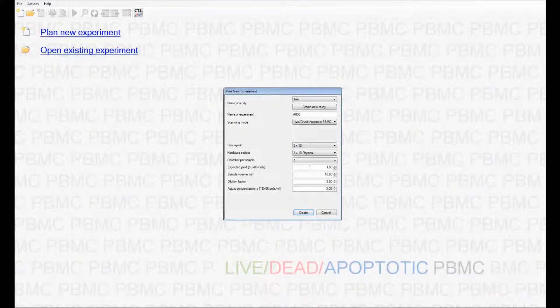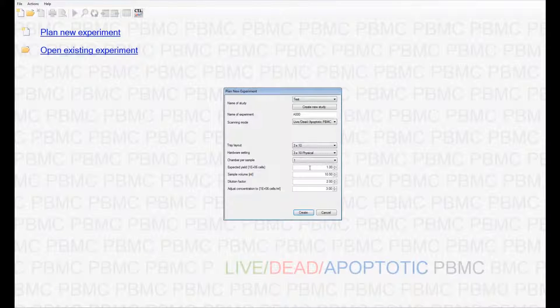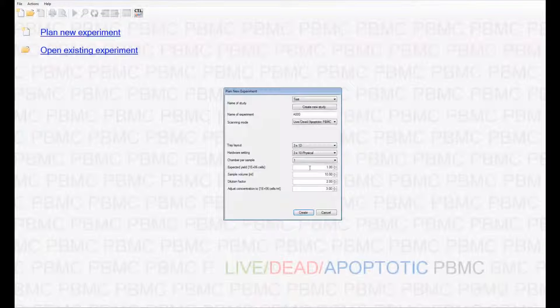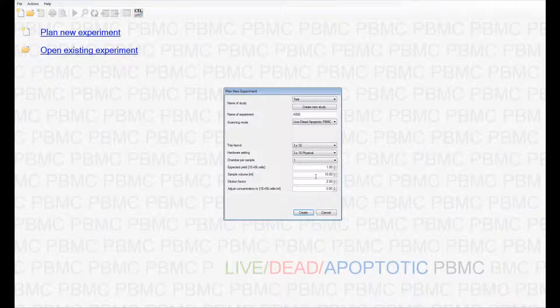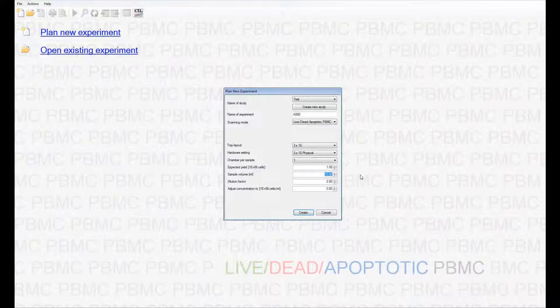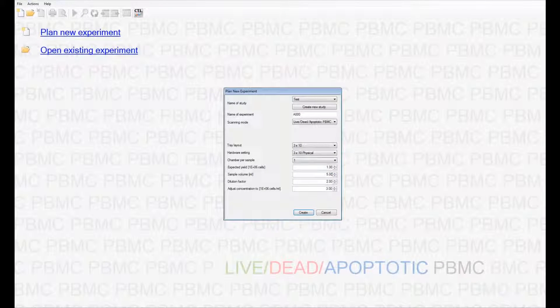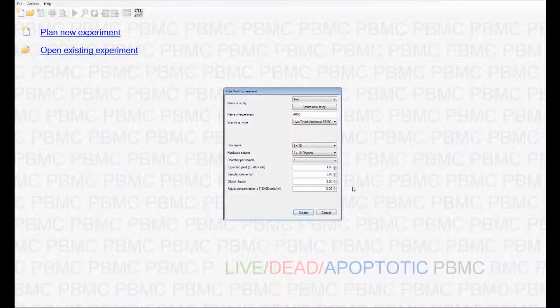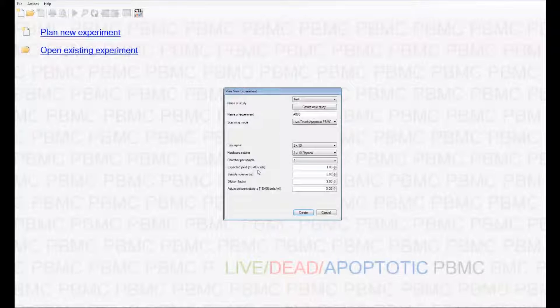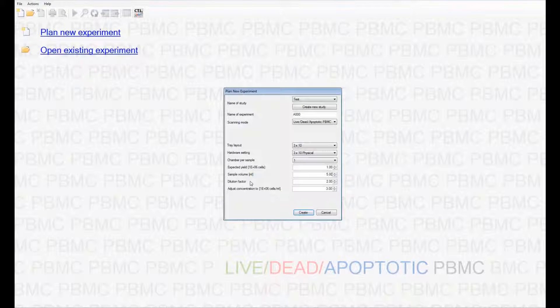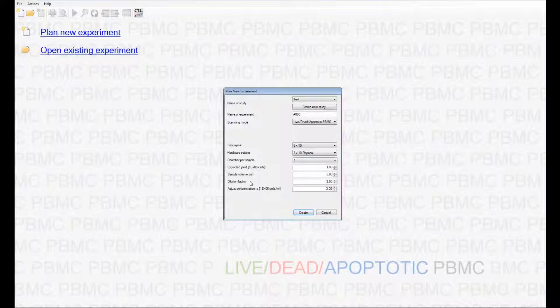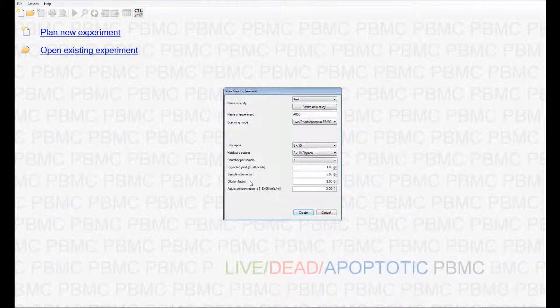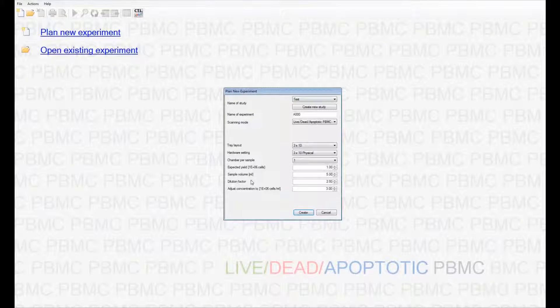A few other parameters that we should specify here are dependent on the particular cell sample that you want to count. For instance, sample volume refers to the volume of the cell sample in your original sample. In my case, that was 5 ml. Expected yield tells you what the recovery percentage is, and dilution factor is a measurement of the dilution of the samples counted with respect to the original sample.